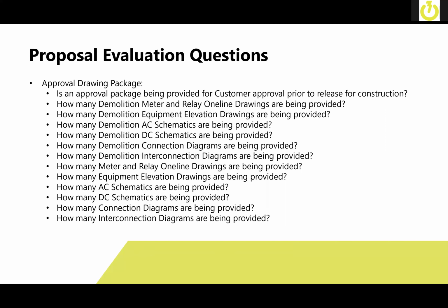Whenever it comes to getting AutoCAD drawings or redline drawings, different companies provide different things. One of the things you may want to ask them is how many meter and relay one line drawings are being provided. Equipment elevation drawings, AC schematics, connection diagrams, and interconnection diagrams showing all the new equipment that's being installed.